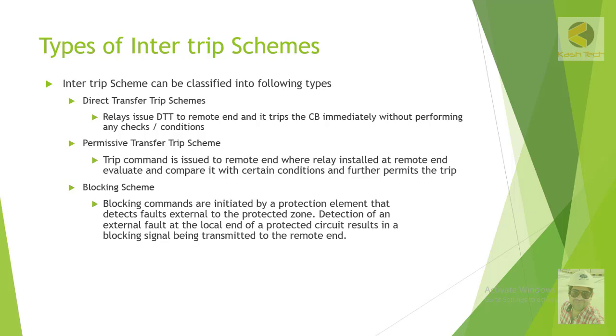The second type is the Permissive Transfer Trip scheme. In this scheme, a trip command is issued to the remote end, where the relay installed at the remote end evaluates and compares it with a certain condition, and further permits the trip.